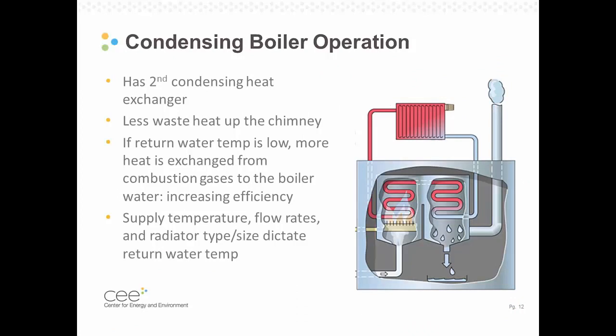So I'm going to try and illustrate why it's so important for that return water temperature to be low in order to get condensation out of the gases. Because condensing boilers have a secondary heat exchanger that is meant to extract even more heat out of that combustion gas, that is being passed next to the return water temperature. So the lower the return water temperature, the better the heat transfer into that water is. So again, the lowest that we can make that return water temperature, the more likely that we'll have condensation. And that is how it gets its efficiency.